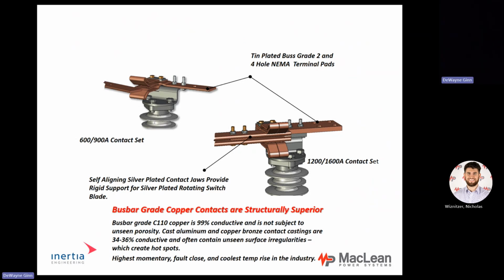Again, on the left, that's a 600 and 900 amp contact set with the blade going into the jaw. Again, we silver plate all of that. On the right is a 1200 and 1600 amp contact set, which would be a dual blade. Each one of those blades is rated at 600 amps.